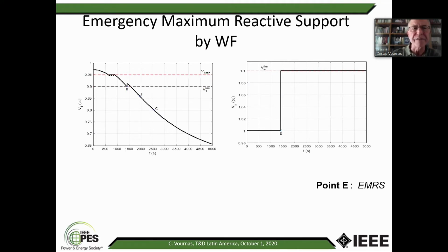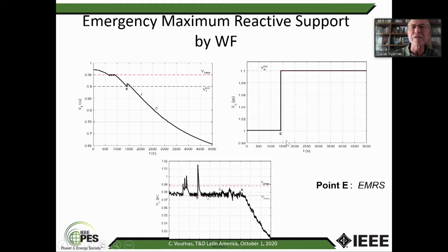Now, let me show you what is the emergency reactive support. Point E, as you see, is where the voltage drops below the 90%. This is the voltage at the primary of the substation. And you see directly, I jump from 1 to 1.1 per unit. And here you see the voltage, first the capacitors, then you have this increase because of the emergency support. You have the limits here. And in this one, you see the voltage on the primary side. With, sorry, the secondary side, where you see the 3 capacitors. And when you have this large jump to 1.1, you see also the LTC is working to reduce the voltage.